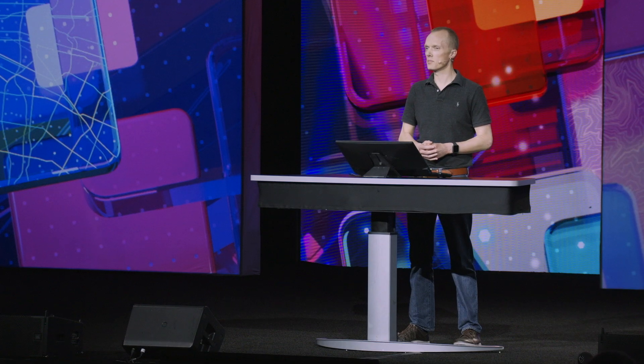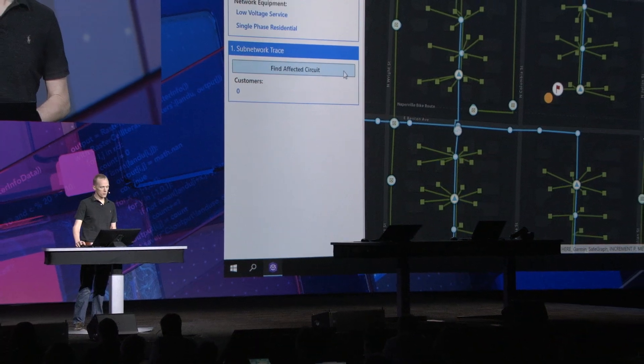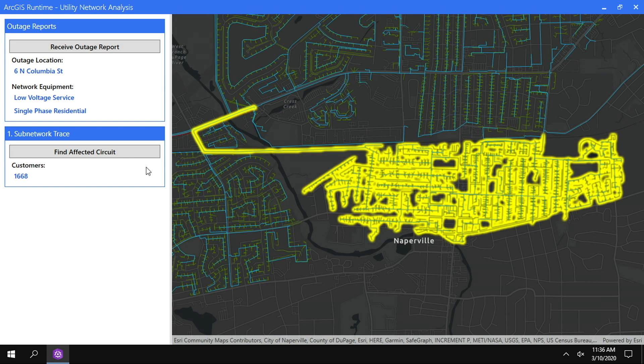Our operations team has received a report of an outage and sent that to us in our truck. We use the ArcGIS Runtime API to quickly determine the address and the equipment of the outage location. In this case, it's a low-voltage service single-phase residential device, or meter. But it's unlikely that it's just this one customer without power — it's more likely that the entire circuit is out. Therefore, the first question we want to answer is: what's the scale of the outage? How many customers are without power right now? Running a sub-network trace sends a request to the utility network web service to trace the entire circuit and tells us that we have over 1,600 customers currently without power.